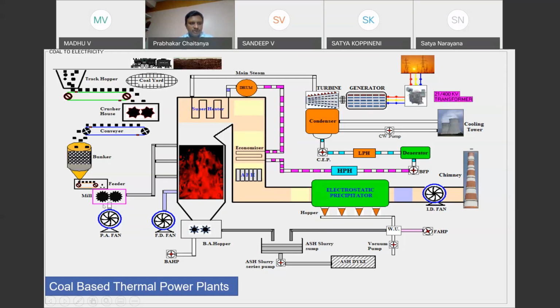Here we have a feeder. Whatever coal is in the bunker is fed into a mill, where it is pulverized, meaning it is changed into powder form. Then, with the primary air fan, the coal is lifted from the mill and let into the boiler.